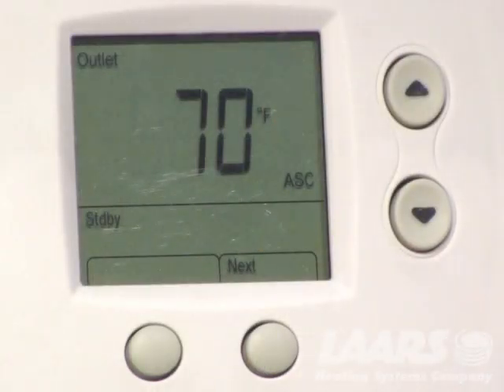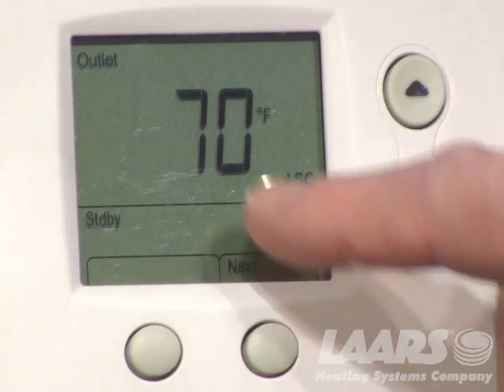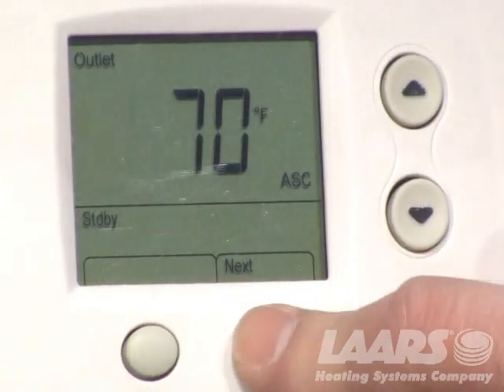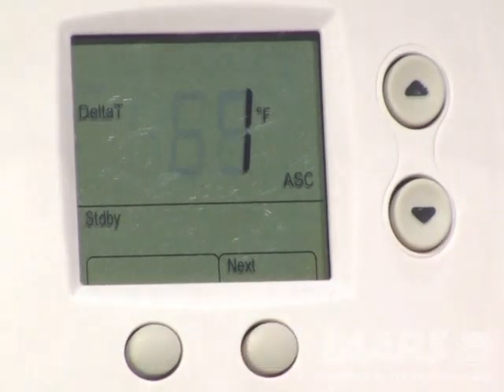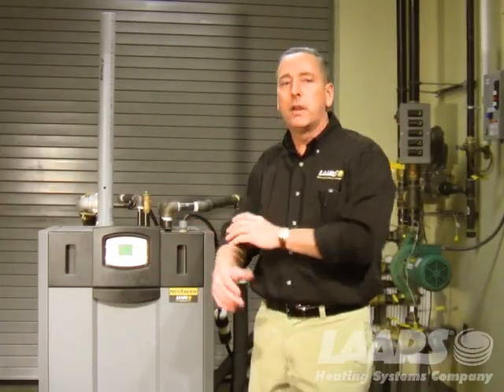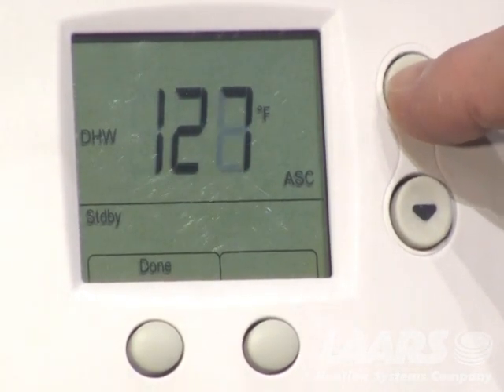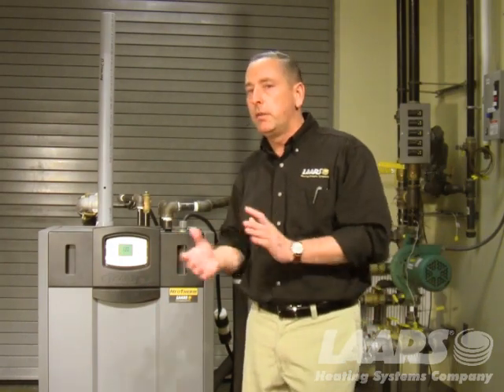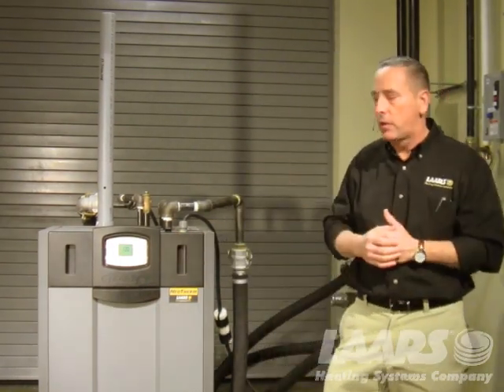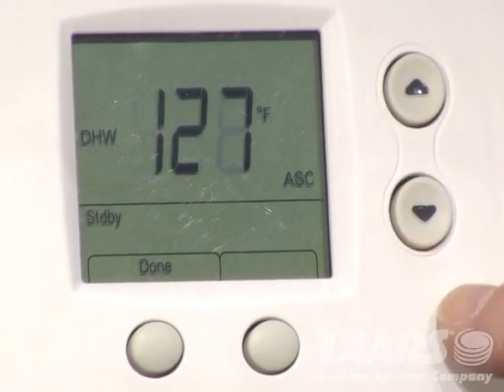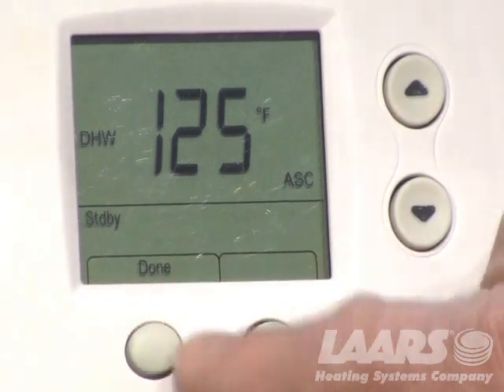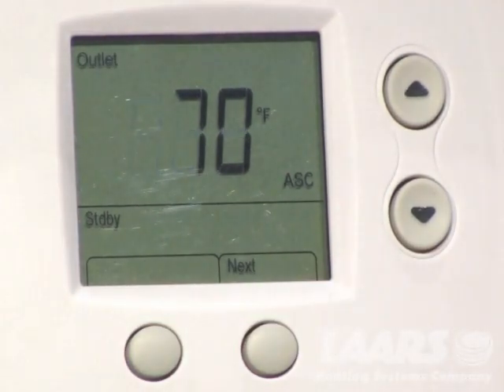Next, we're going to set up domestic hot water. That is in the user mode — simply press the next button to scroll through that menu. Starting at the outlet screen, press next to show inlet, next again for delta T. The boiler is not running, just sitting idle, so we only have a one-degree delta T. Press next again and it will show DHW. In that screen, use the up arrow to increase the temperature to your desired set point. Keep in mind, you should have mixing valves on your system to avoid scalding issues. Once you set your domestic set point, press and hold the done button so it stores the temperature.